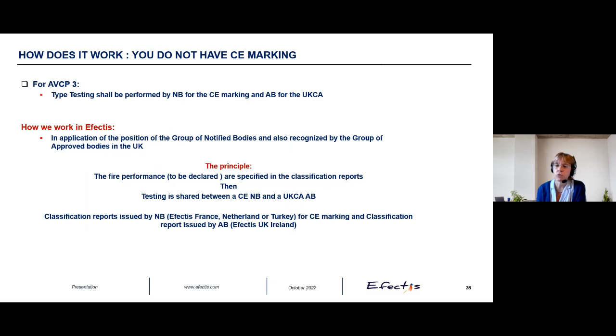The principle is that fire performance to be declared is specified in the classification reports. The testing is shared between the CE notified body and the UK approved body. Basically, we perform some tests in Efectis UK Ireland, and some tests in one of the other entities of Efectis. Based on this, we put together all this testing, all these test reports and exact reports if they have been issued, and we issue two classification reports—because we will need two: one for CE, with a CE notified body number, and one for UKCA, issued by Efectis UK Ireland. This allows us to limit the number of testings needed while covering both CE and UKCA.